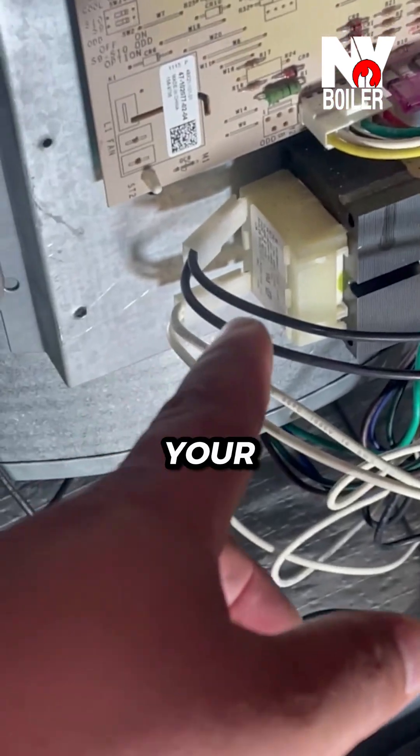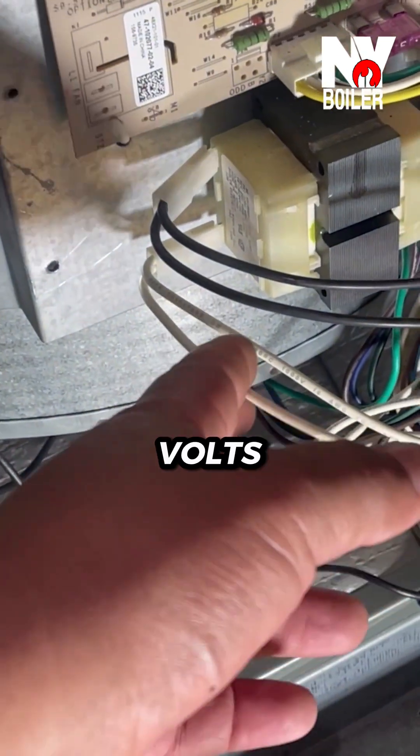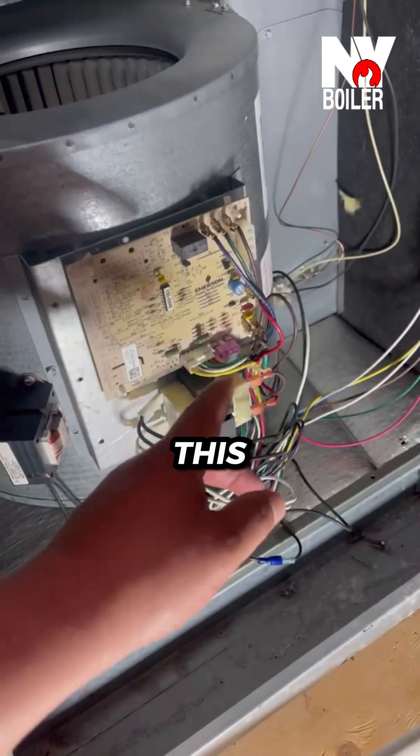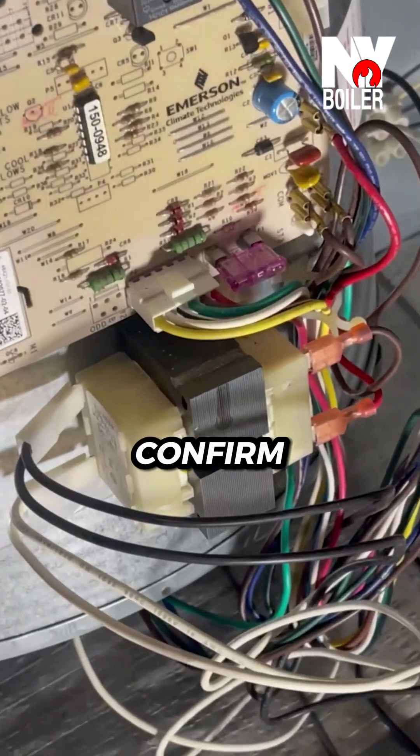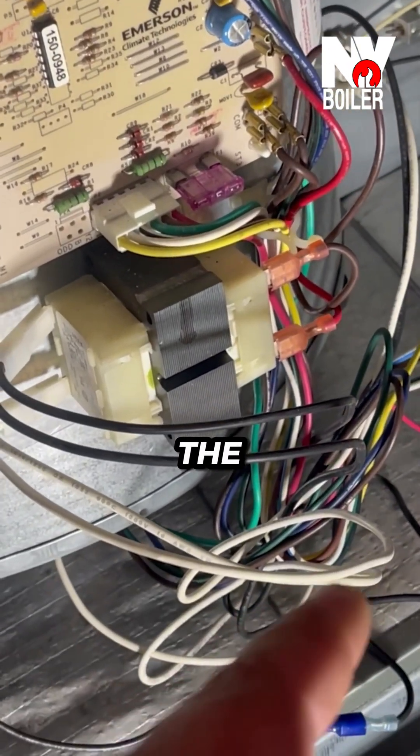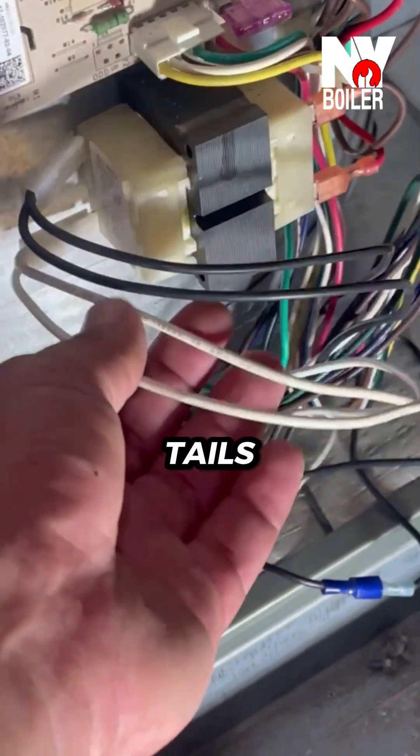Here's your high side which is 115 volts, neutral and hot. Also, this is your control. So I confirmed I got 115 volts going to the motor because one of these pigtails are going to the motor.